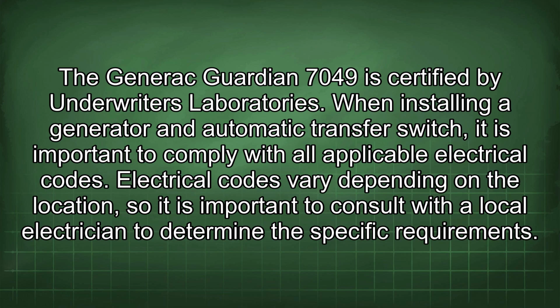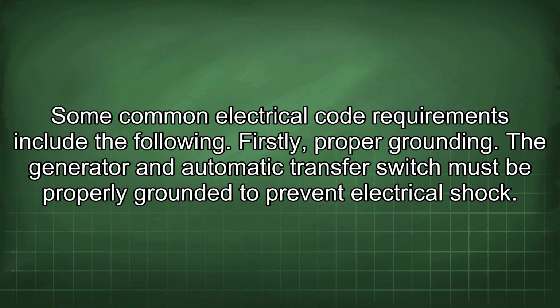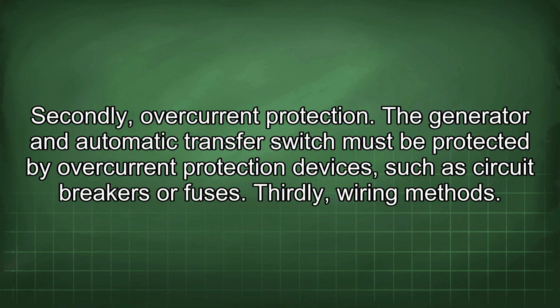When installing a generator and automatic transfer switch, it is important to comply with all applicable electrical codes. Electrical codes vary depending on the location, so it is important to consult with a local electrician to determine the specific requirements. Some common electrical code requirements include the following. Firstly, proper grounding. The generator and automatic transfer switch must be properly grounded to prevent electrical shock. Secondly, overcurrent protection. The generator and automatic transfer switch must be protected by overcurrent protection devices, such as circuit breakers or fuses. Thirdly, wiring methods.